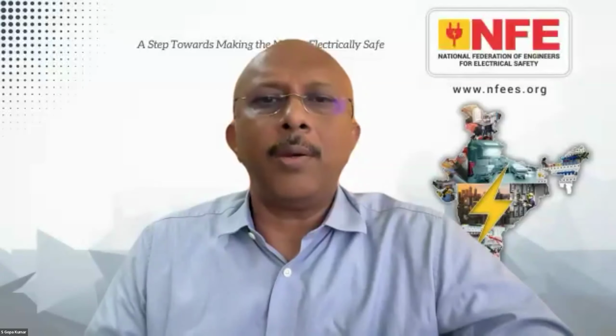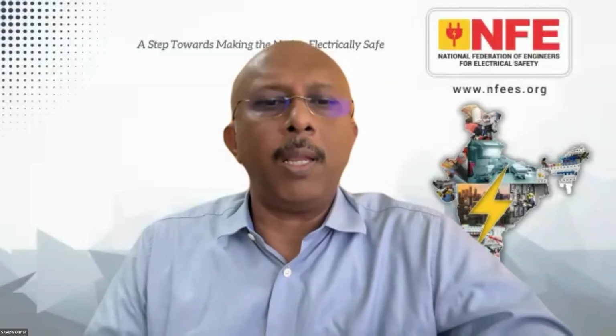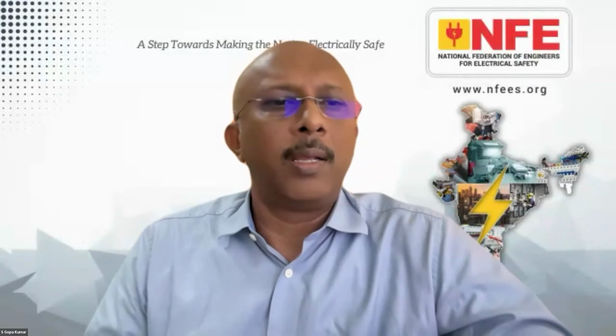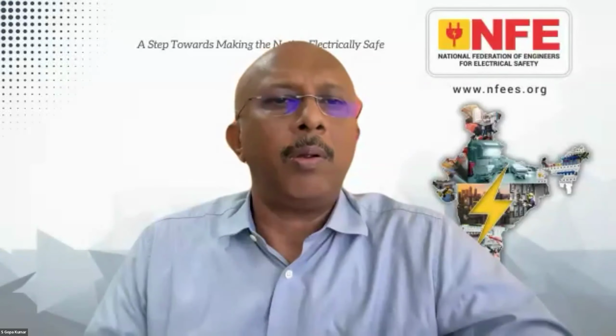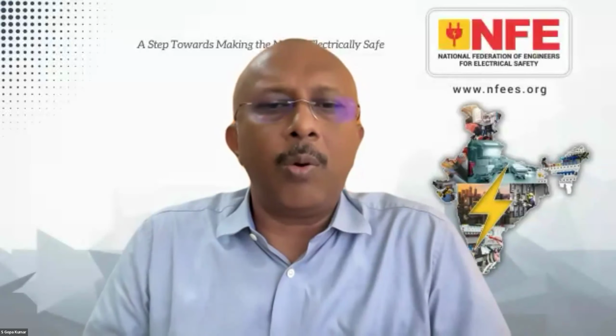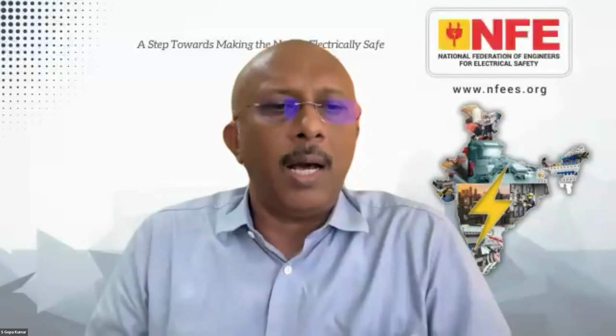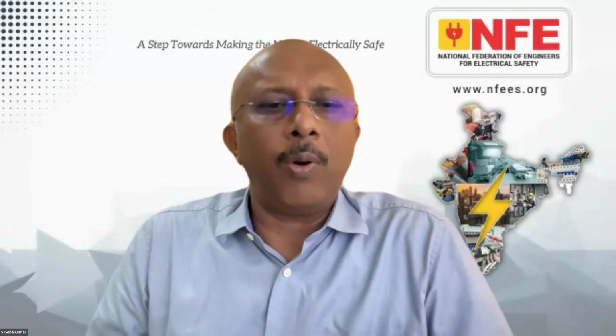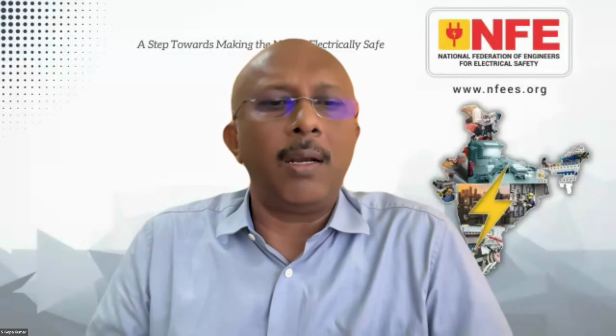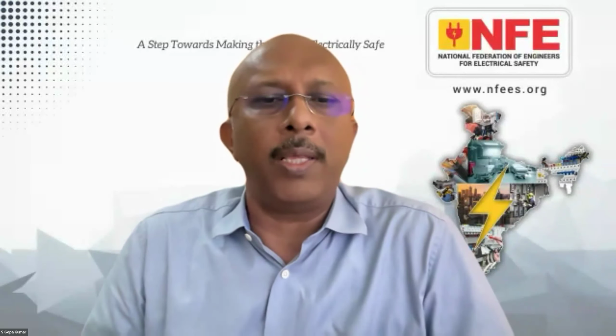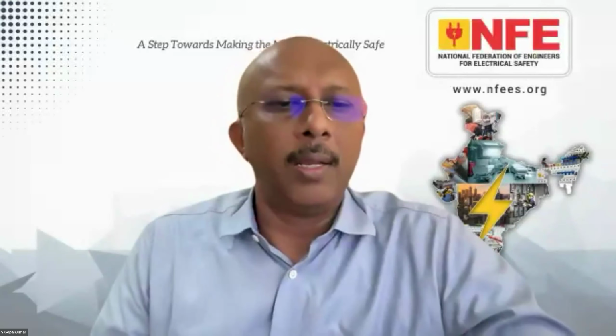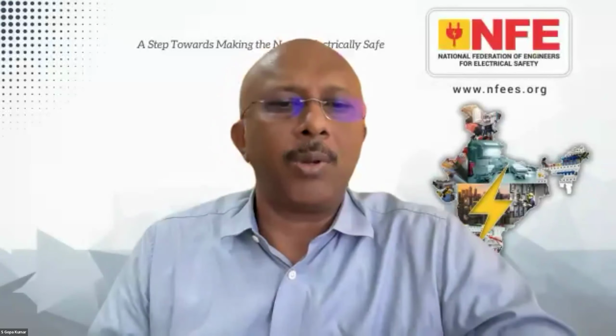Actually, unbalanced load has nothing to do with residual current. Whatever the unbalanced load, it will go through the neutral conductor. Mr. Gerard, would you like to answer something? Not my real topic, let's say. I think you're more familiar with that. Yes. So unbalanced load has nothing to do with RCDs. An RCD's job is to disconnect the supply only if there is a residual current, in the sense that a current escapes from the circuit, from all these three-phase wires and the neutral conductor. So practically, unbalanced load is not a subject for the RCD. It doesn't matter whether the load is balanced or not. It's only the presence of residual current.